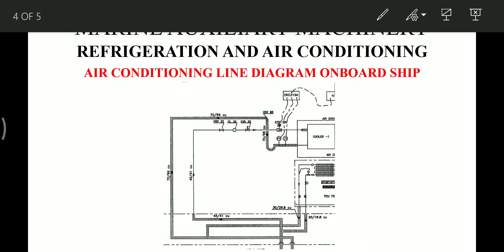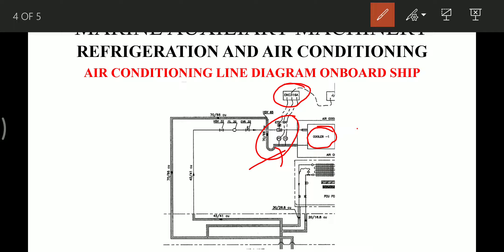In the evaporator diagram we have cooler number one — there are actually two coolers but only one is shown here. The expansion valve is electronically controlled. It takes signals from the pressure transmitter and temperature transmitter installed at the outlet of the evaporator, which send signals to the controller. The controller then signals the expansion valve, which is driven by a stepper motor that adjusts its position to control the refrigerant flow into the evaporator and regulate the temperature.